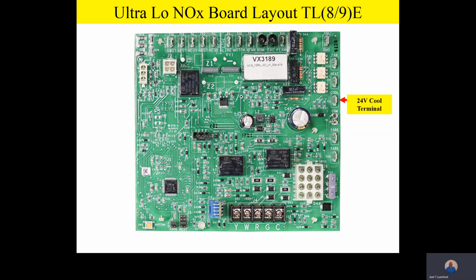This is our cool tap. Now, it should be noted, this cool tap will be energized on the cooling airflow on our unit. When we start talking about a two-stage hookup, please remember this cool speed will actually have to be selected on a speed tap to provide 65% airflow on a Y1 or first stage call on a two-stage cooling unit. But we'll discuss that a little bit later on. So just know that from the factory, we typically ship this on high speed, but you can manipulate that cooling airflow with this cool jumper or this cool terminal for a two-stage product as well.